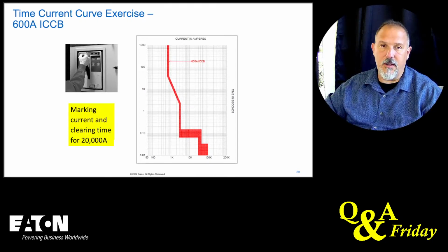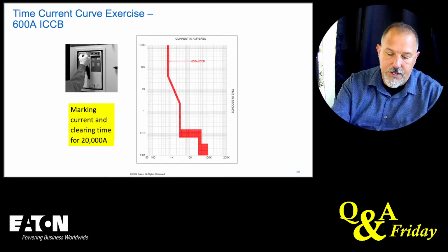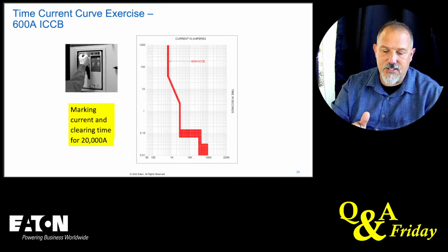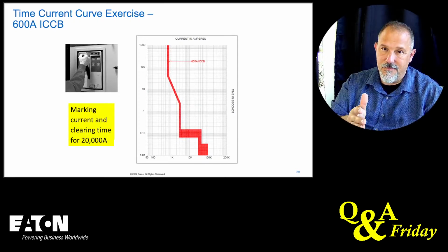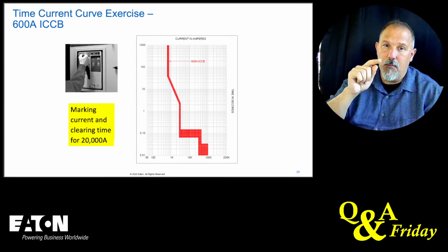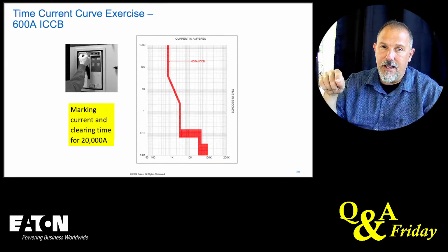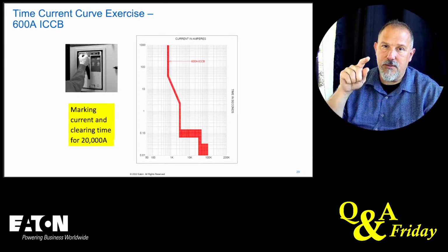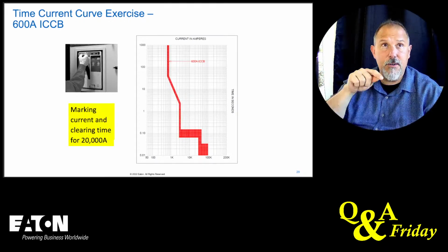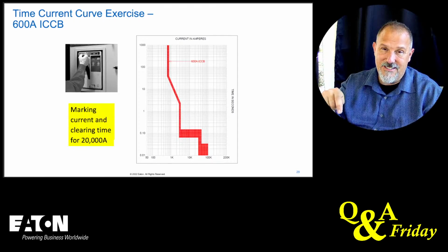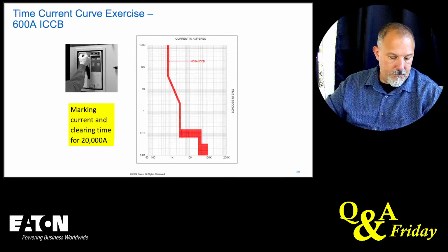It can't be current limiting because a current limiting device is going to trip in less than a half cycle. And how fast is a half cycle? Remember what one cycle is. 0.0167. A half a cycle, 0.008. You're nowhere close to a current limiting device.